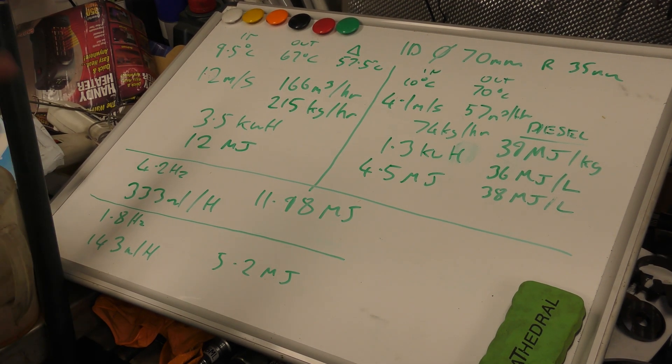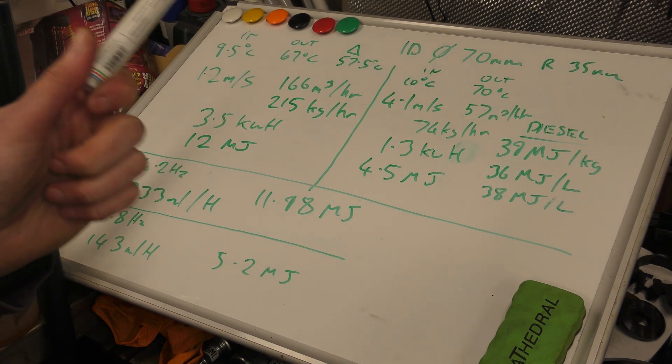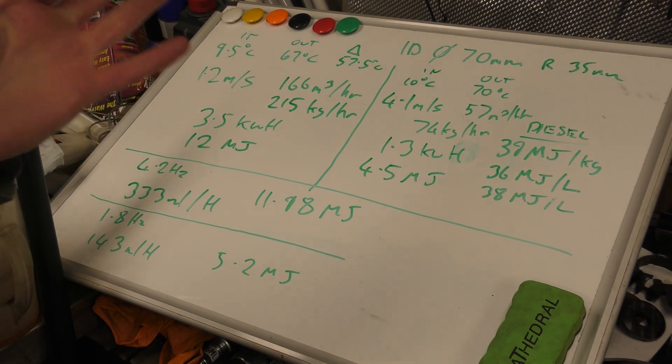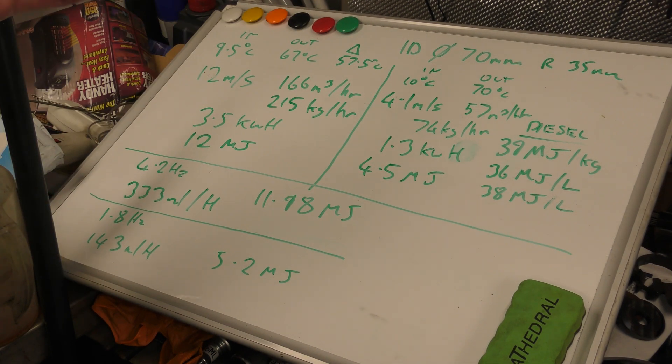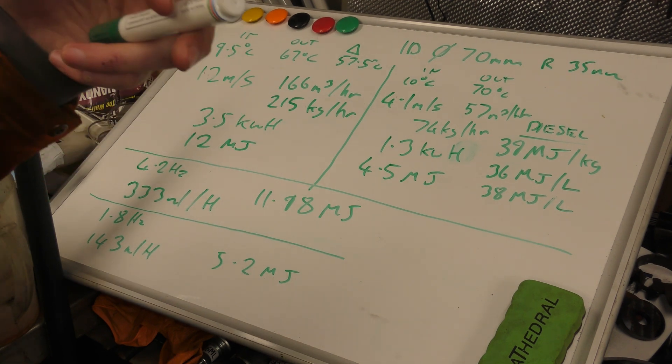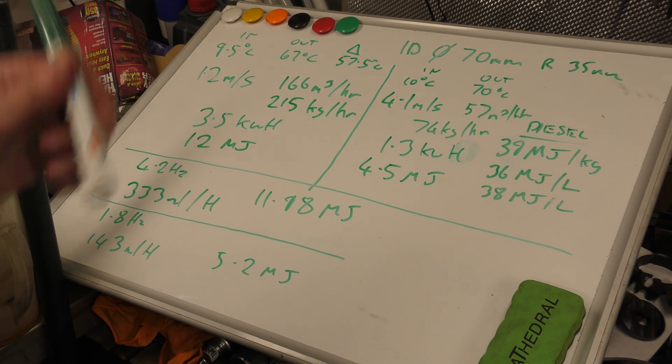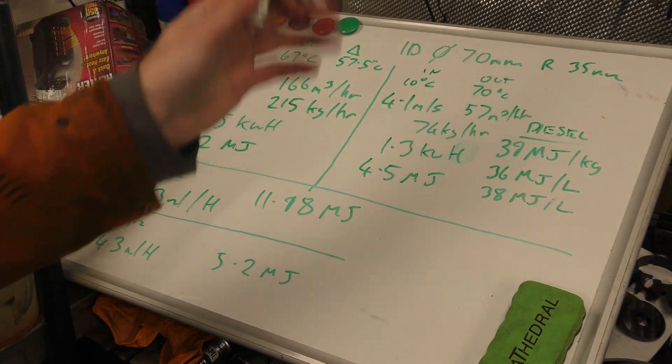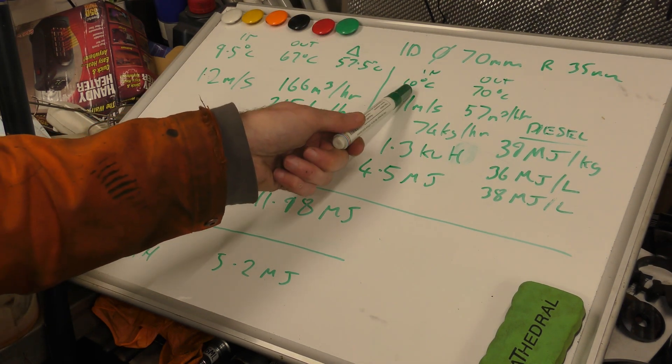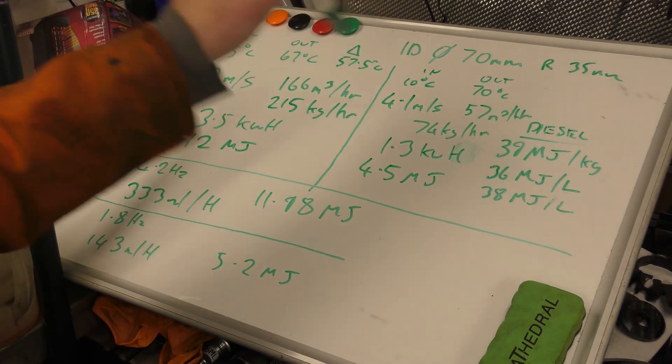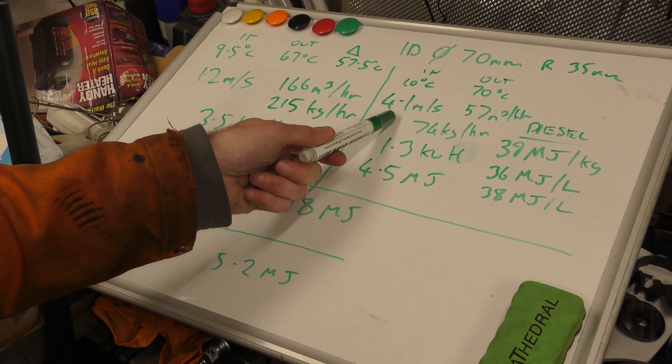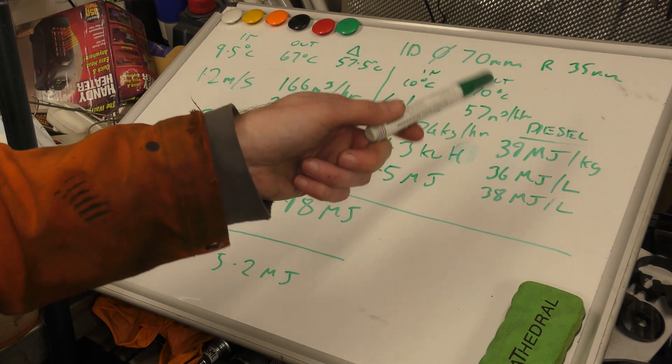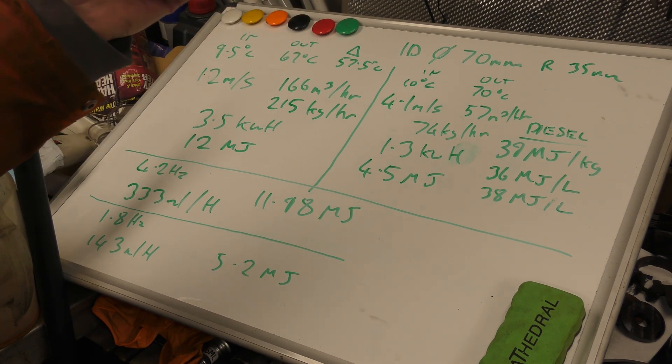I have run the low side calculations. On my heater I have the low set for 1.8 hertz. I should have mentioned that I haven't actually checked what RPM I'm running. It doesn't really make a difference to what we're doing. Obviously your heater depending on what fuel setting and fan RPM setting will depend on any numbers you would get because more fuel, more air, more heat. But on my heater running 1.8 hertz, the intake temperature was 10 degrees. I've gone up half a degree in the workshop. In was 10, out was 70, giving us a delta of 60. Air speed was 4.1 meters per second, which worked out as 57 cubic meters an hour, which is 74 kilograms of air per hour.